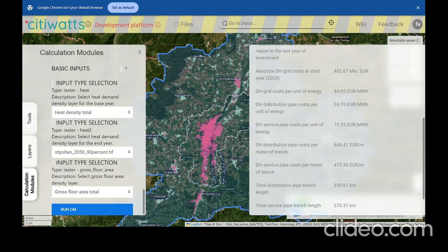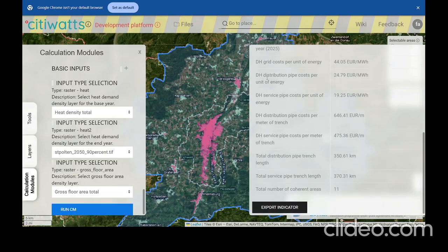And there's a distinction between distribution pipes and service pipes. Service pipes are those pipes which connect the distribution pipe to the buildings. You can see that in this case, for example, service pipes are cheaper, and in total it will cost 44 euros per megawatt hour to connect all identified regions with the given conditions.